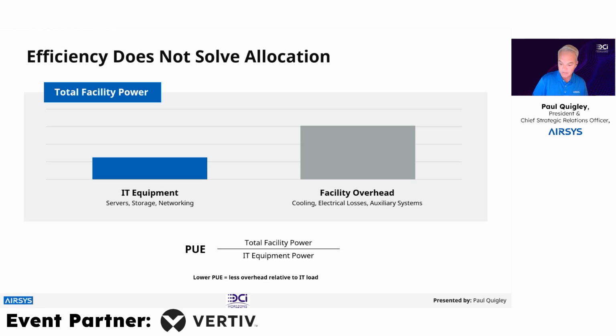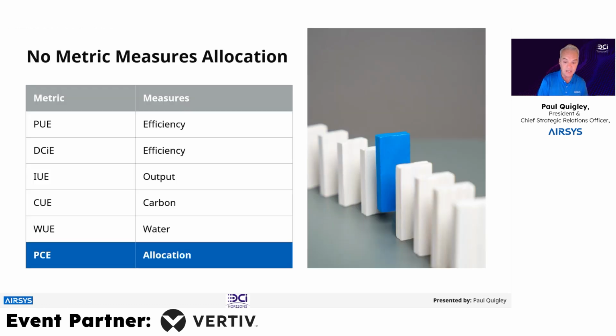But here's the limitation of it. PUE measures efficiency of power usage, but it does not actually measure how the power is allocated within the facility. That distinction is not only important, it's revealing, and it's becoming extremely apparent now that AI is the dominant factor. So while PUE will tell you how well the system runs, it does not—and was never designed to—tell you how much of your available power can actually be used for compute.